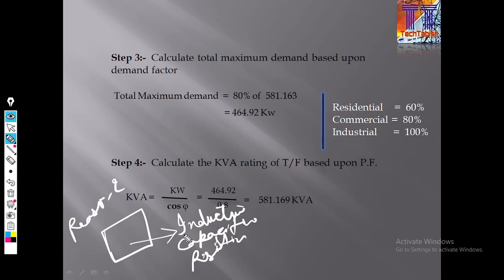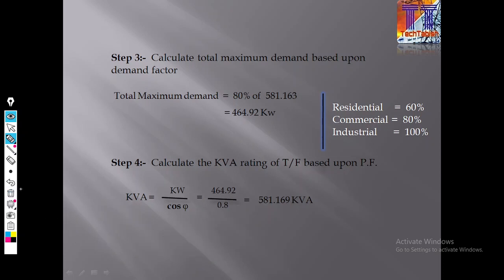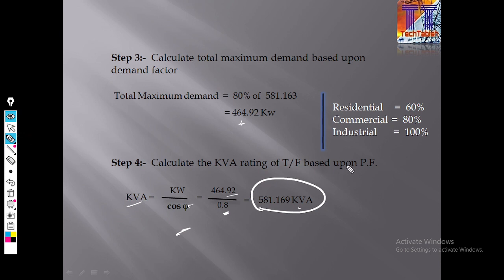We don't know which type of load is given to this transformer. Okay, so that's why we are giving the rating in kVA to the transformer. Okay, so kVA equal to kilowatt upon cos phi, the power factor. 464.92 divided by 0.8, so we got 581.169 kVA. Okay, so this is basically based upon power factor.